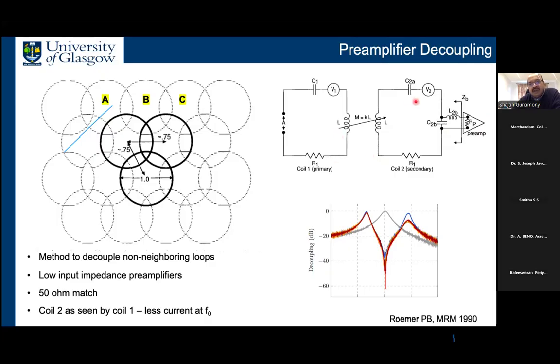But if you look into coil 2 from coil 1, you have capacitor C2 and L2, and then this 1 ohm impedance from the preamplifier, which forms a resonance circuit. The property of a parallel resonance circuit is that at resonance it creates a high impedance. So across C2, it creates a high impedance. That's what coil 1 sees. When there is high impedance, there is low current, so you have low current at that frequency. That way, coil A and coil C don't see each other.